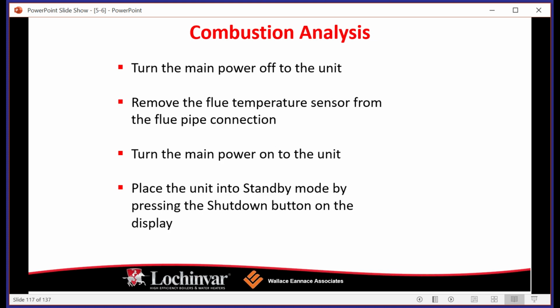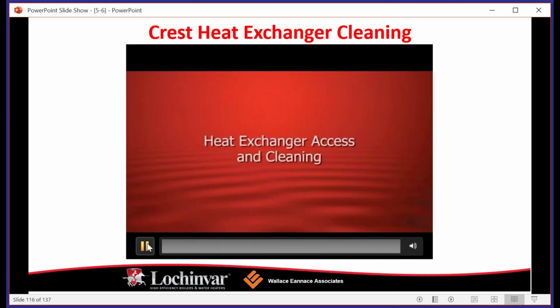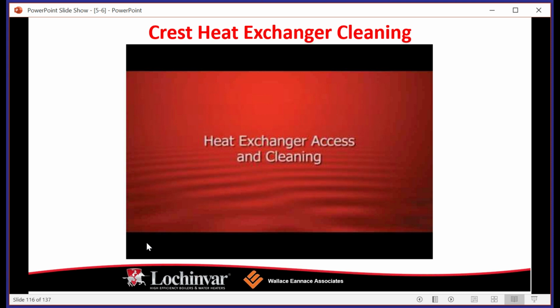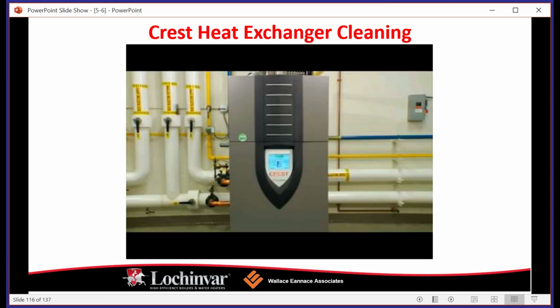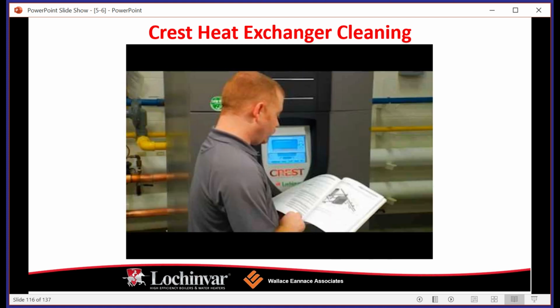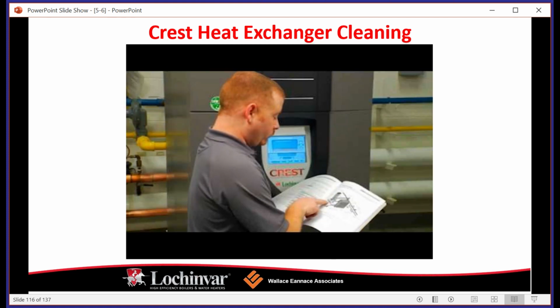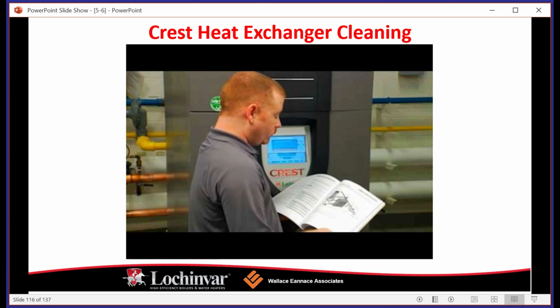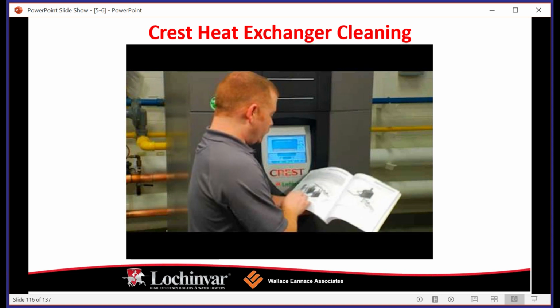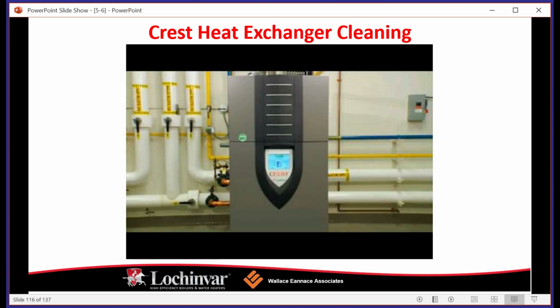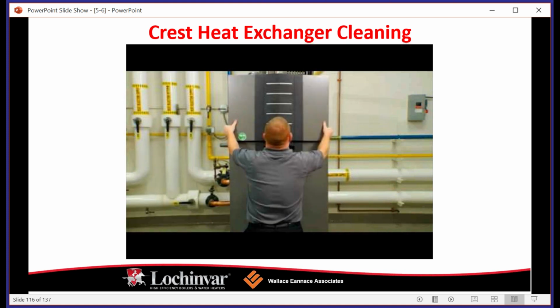Maintenance and service, we're going to go through, and I know it sounds simple, but check wiring and connections. Really do that. Take a minute to make sure that your spade connectors all look solid. Nothing's vibrated loose. Not that you see a ton of environmental vibration, but the blower or something like that, if you've got bad combustion, can create vibration towards the fan, and it is possible for stuff to go through. So startup, checkout, and performance verification, you're going to visually inspect the flame.